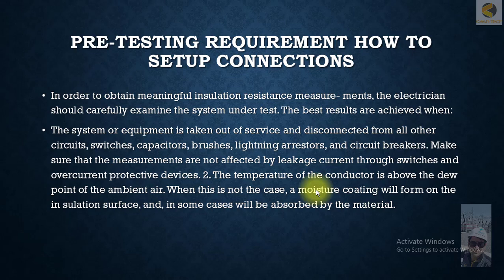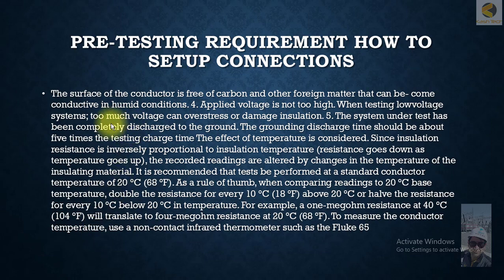Make sure that the measurements are not affected by leakage current through switches and overcurrent protection devices. The temperature of the conductor should be above the dew point of the ambient temperature so that moisture does not affect the reading. When this is not the case, moisture coating will form on the insulation surface and in some cases will be absorbed by the material.